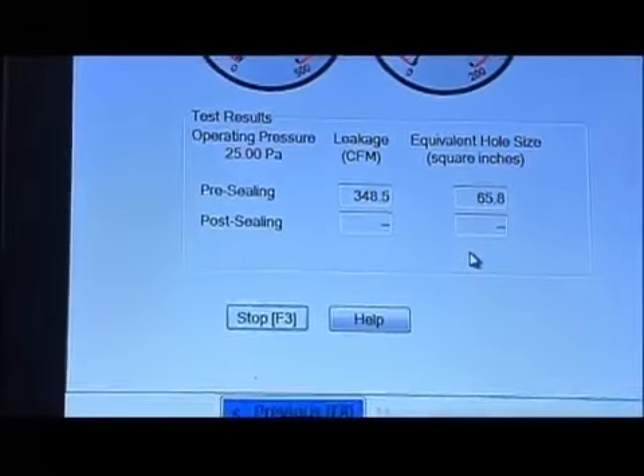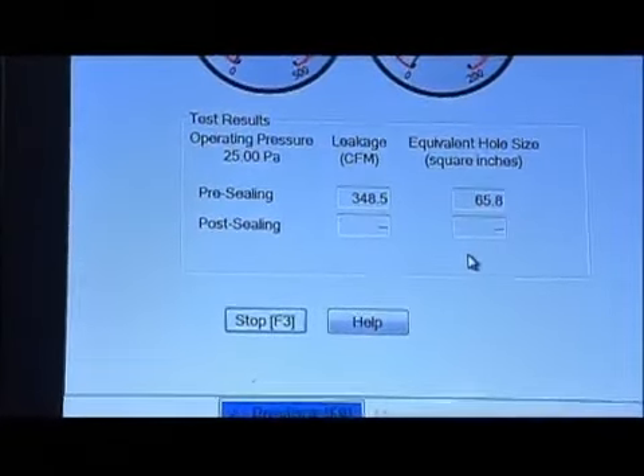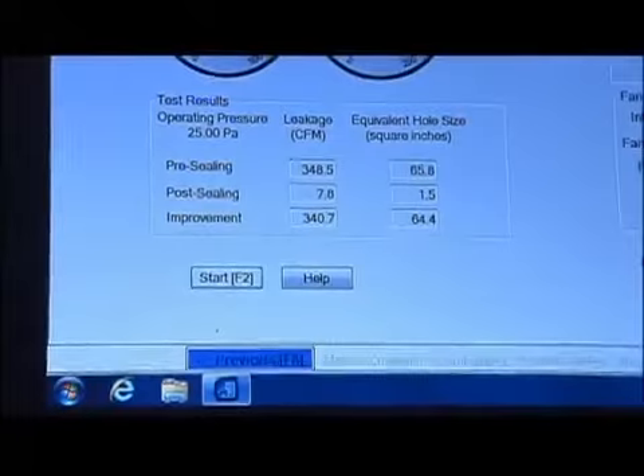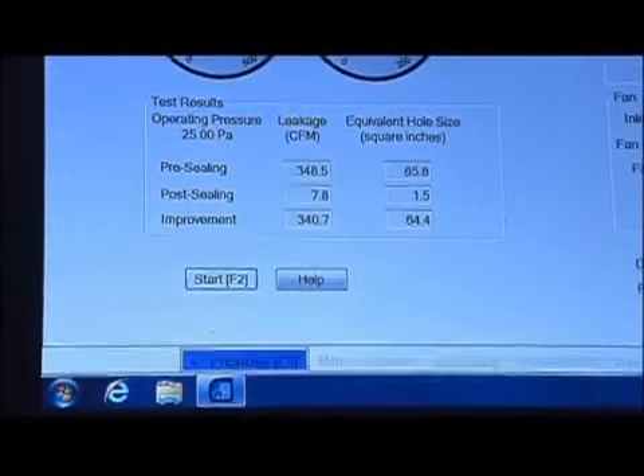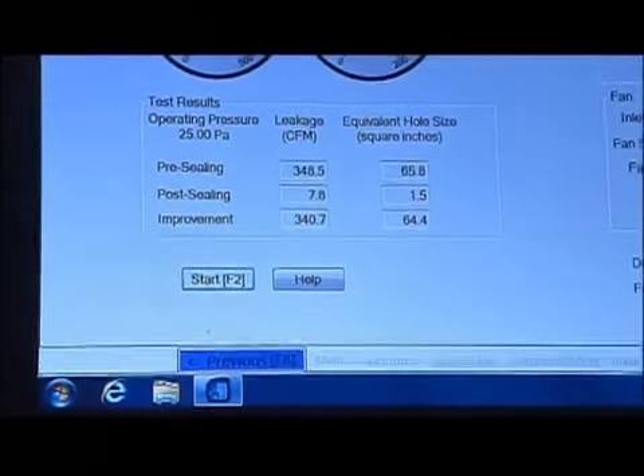So where are we at? When we initially started, we were leaking 348 CFM of air, equivalent to a 65.8 square inch hole. That's where we started. Now, post-sealing, we got it down to 7.8 CFM of leakage, equivalent to a 1.5 square inch hole. Wow, that's huge.